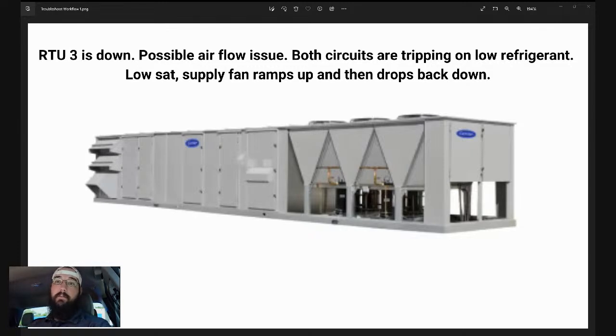One way to do that is, well, we have an interface on this system. Hopefully it works to some degree, but if you go to the pressures section under the air side inside of that Carrier Navigator, you'll get to the active static pressure. If you lock that drive off at a certain hertz, you could look at whatever that static pressure is, then go around and unhook the static pressure sensor and plug it into your manometer and see what the reading is, and let that help guide you. How close are we? If we're within a tenth of an inch, then you're probably fine. It's not a static sensor issue. What else is going on here?